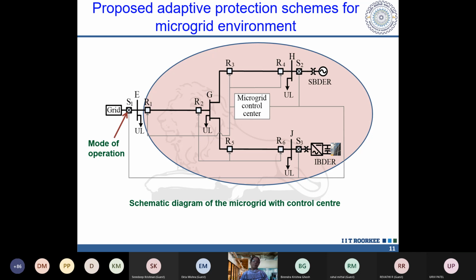Power quality issues will come. Personnel safety may be at risk because some people working in this substation do not know that the main grid is off and still they are working. They may get shocked, and there are many other protection issues that will come into the picture. So it is very essential to detect such a mode of operation of the microgrid, and we have developed many techniques, like passive islanding detection, active islanding detection, and hybrid islanding detection. Hybrid means both passive and active techniques are merged together, and there are also communication based techniques.